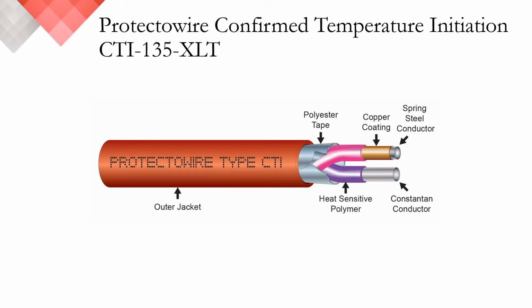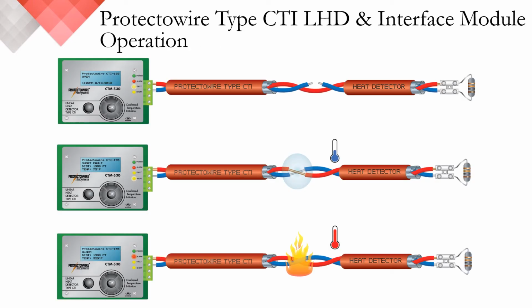For those of you looking for more information on this technology, as I mentioned earlier, we have a few additional webinars and short introductory videos that introduce it, located under the Resources tab on our website. Unlike standard digital linear heat detectors, our CTI series has four operating conditions. During normal condition, the end-of-line resistor conditions the circuit, allowing the CTM series interface module to know everything is working properly. Note that this image is not displayed on your screen here. Moving on, if and when current flow stops, our CTM series interface module will initiate an open fault or a trouble condition, similar to our standard product.